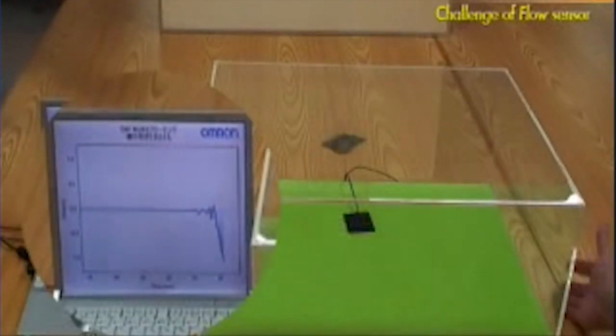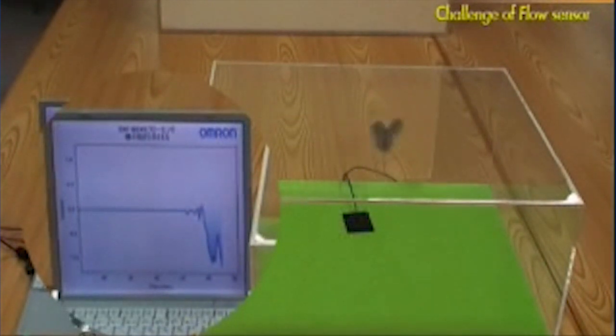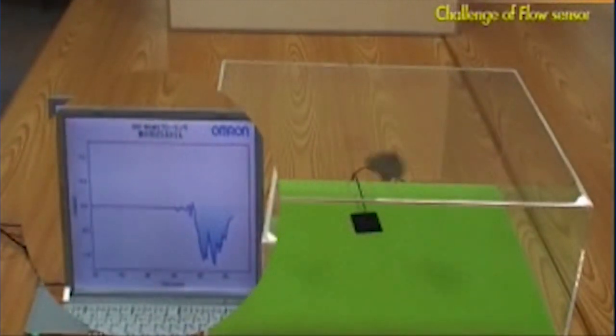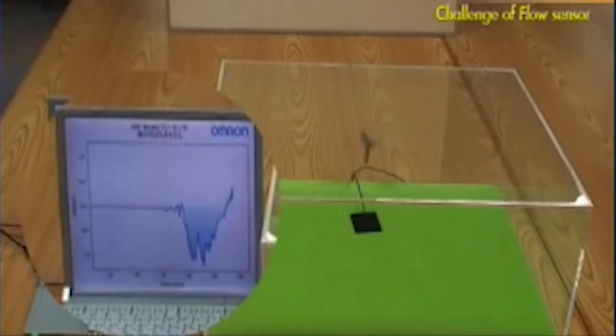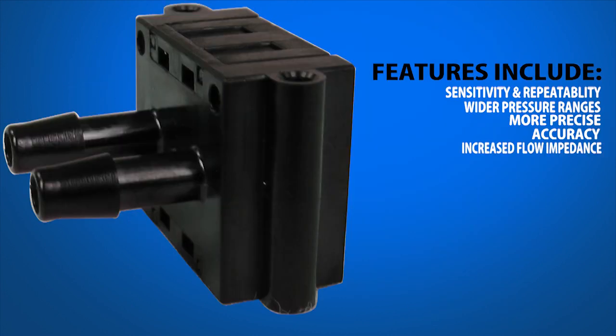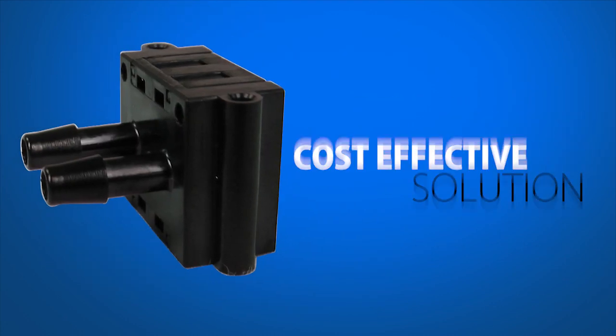Features include superior sensitivity and repeatability, wider pressure ranges than the commonly used capacitance type and piezoelectric type differential pressure sensors, more precise and less influenced by temperature than conventional analog output sensors, a digital correction algorithm that achieves an accuracy of ±3% of reading, and increased flow impedance, reducing the influence of the bypass pipe length and diameter.